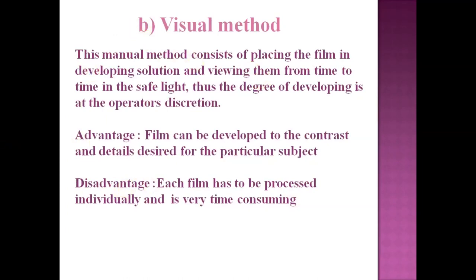The visual method is a manual method consisting of placing the film in developing solution and viewing it from time to time under a safe light. The degree of developing is at the operator's discretion. Advantage: film can be developed to the contrast and detail desired for the particular subject. Disadvantage: each film has to be processed individually and it is very time consuming.